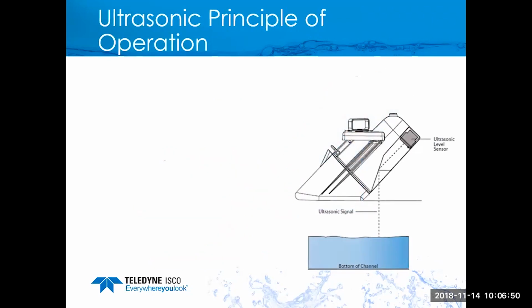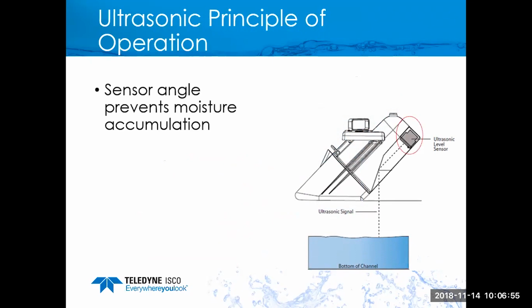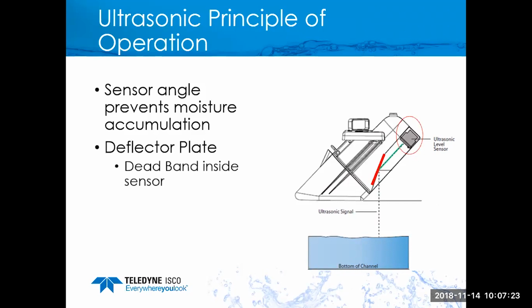Before we get into the laser, let's talk about the principles of operation of the ultrasonic. The ultrasonic is mounted again in the back of the sensor. When we designed this, we talked to a lot of customers, and one of their recommendations was to mount it at an angle. The reason we did that is so the moisture, whether it's recovering from submergence or just humidity in the environment, will just drip off the ultrasonic face, so we will not have to clean it. It has a built-in deflector plate, which is built into the molded body housing. It reflects off of that, transmits, and hits the water.